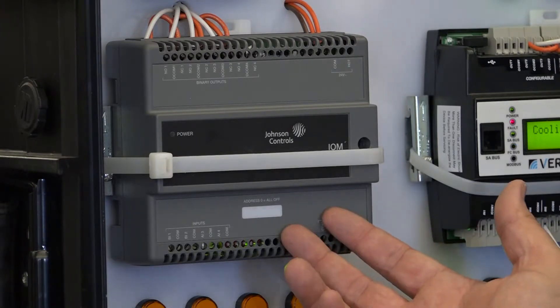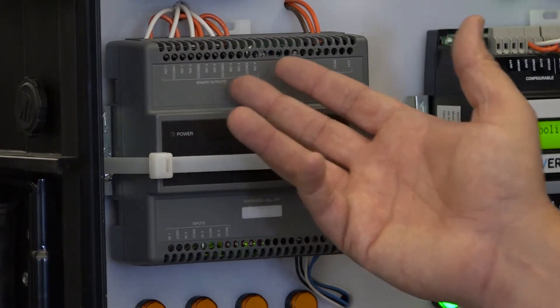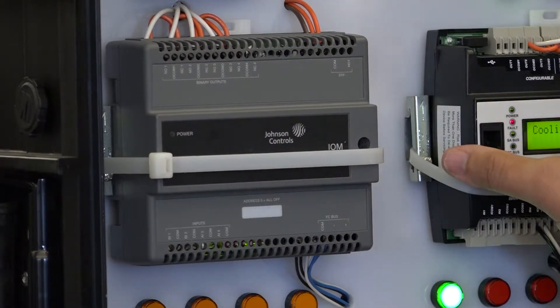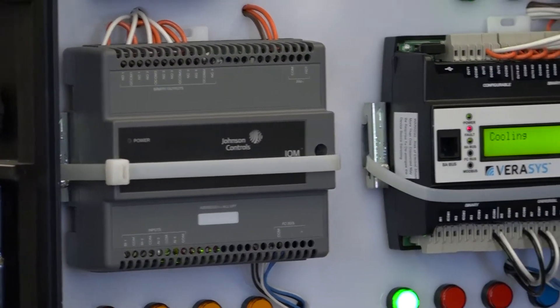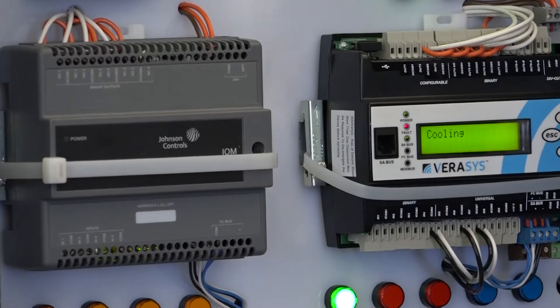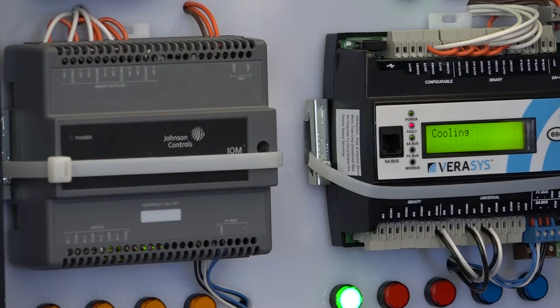We can also use it to turn on other outputs when a schedule in another device is occupied. For instance, with a rooftop unit or single zone unit, when that's occupied you can turn on an exhaust fan or toilet exhaust fan. We can do those types of interlocks as well.